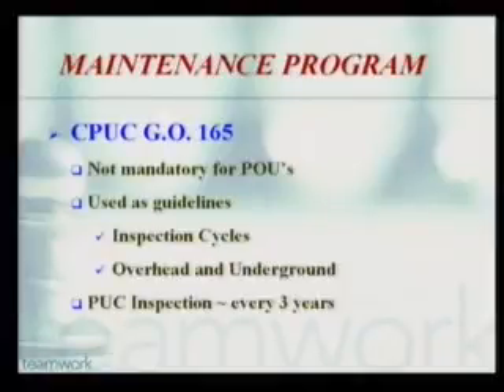The recommendation is there should be at least one visual inspection per equipment per year. If it's overhead, it should be detail inspected once every 5 years. For underground devices, it should be once every 3 years, detailed inspection.